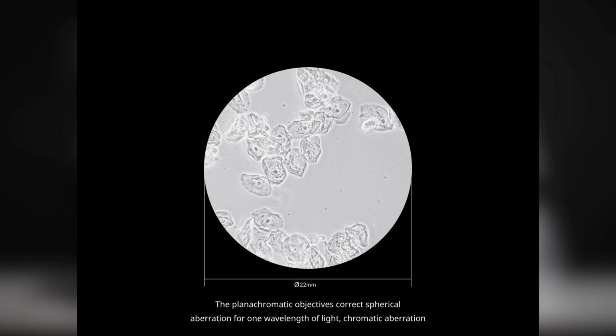The planachromatic objectives correct spherical aberration for 1 wavelength of light, chromatic aberration for 2 wavelengths, and correct field curvature by 90%, when used with eyepieces that have a field of view of 22 mm.